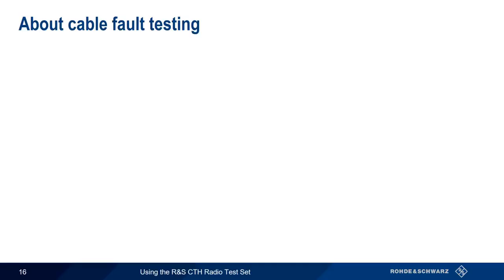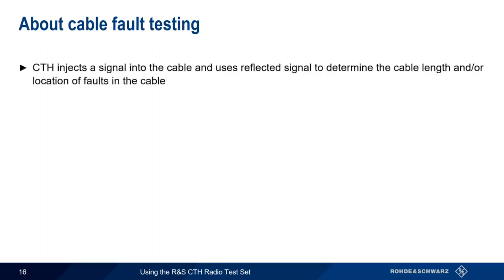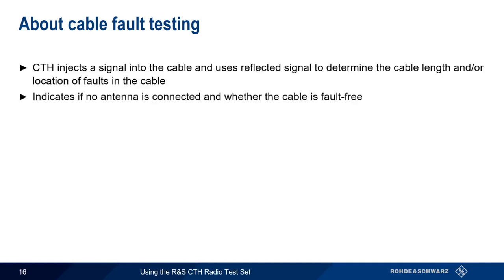Now let's look at Cable Fault Mode. When a cable fault test is run, the CTH injects a signal into the cable under test. The CTH then analyzes the reflected signal to determine the cable length and/or the location of faults along the cable. This is sometimes referred to as a distance-to-fault measurement. The CTH will also detect and display if no antenna is connected, or if there are no faults detected in the cable.